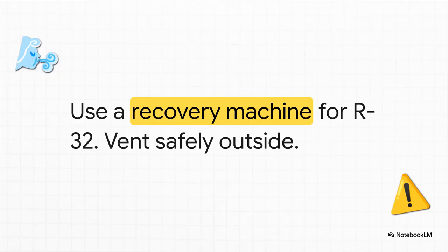Now, what about venting? The rules depend entirely on the gas. Because R32 has a moderate global warming potential, it is illegal to just vent it. You must always use a recovery machine. Hydrocarbons like R290, however, are a little different. While a recovery machine is still preferred, they can legally be safely vented directly outside. You'd use piercing pliers and a long hose with an extractor fan, provided you're in a completely safe, ignition-free outdoor area.